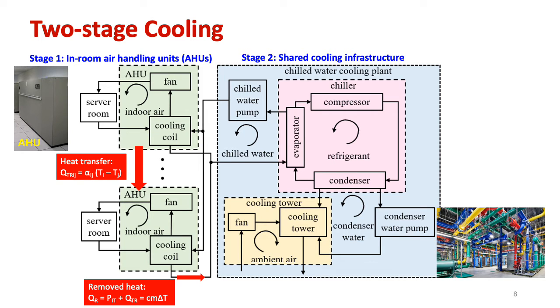The heat removed by an AHU is the sum of the IT load and the total heat from other rooms, which is modeled by a linear function of the mass flow rate and the temperature delta of the water or air going through the AHU. The heat removed by the cooling tower is the sum of the power consumption of the chiller plant and the total heat generated by all the server rooms, which is also modeled by a linear function of the mass flow rate and the temperature delta of the water or air going through the cooling tower.